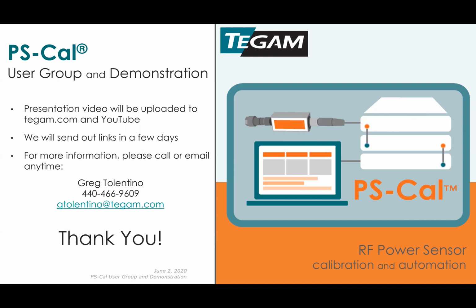I will say that our goal with PSCal is to actually take a different approach with it, and this will not be in the next release, maybe the release after. Our approach is going to be to use the 2505 as your 50 megahertz reference. So as part of the calibration, the 50 megahertz reference will be performed. What we hope is, first of all, it helps answer this question: do I need to do this disconnect and connect to the device under test power meter power reference? And the answer then will be no, because you're doing it on the TEGAM 2505.